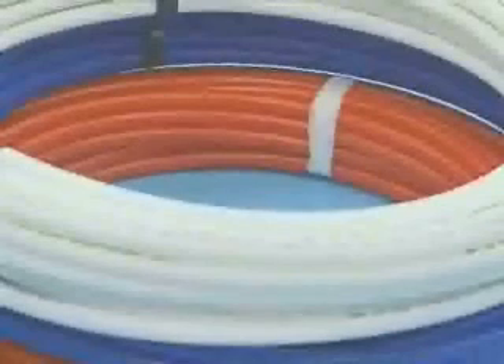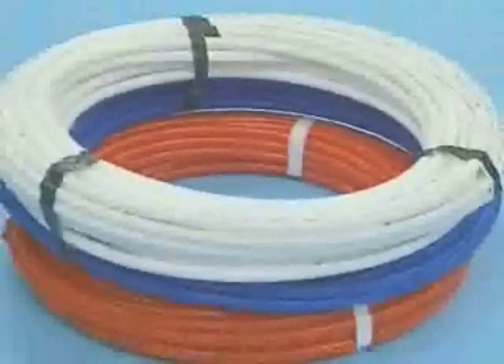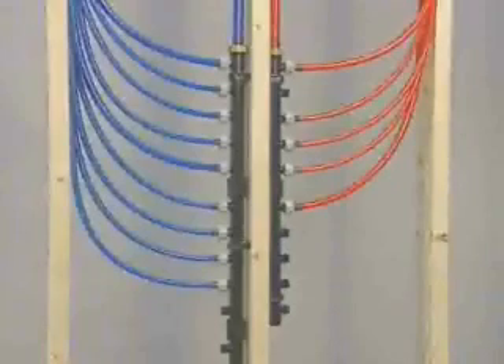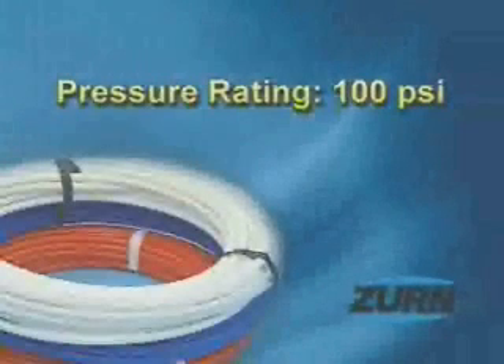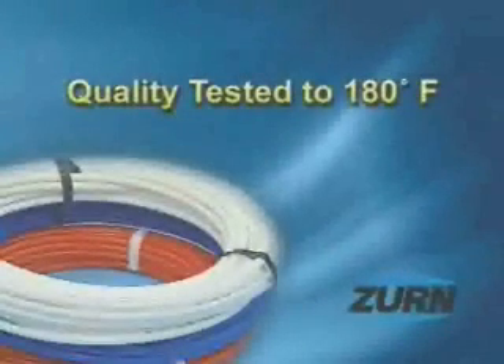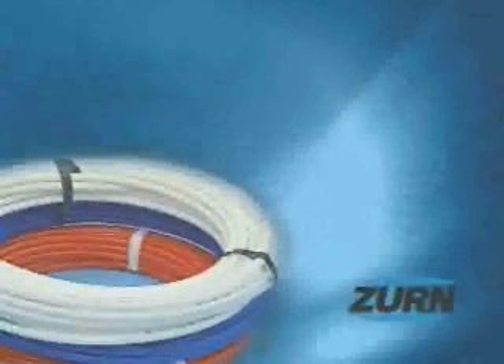Zurn PEX tubing is available in white, red, and blue. These color options make color coding of hot and cold water lines easy if desired by the plumber. The pressure rating for Zurn PEX tubing is 100 PSI, more than enough for residential plumbing applications. It is also safe because it is quality tested at temperatures up to 180 degrees Fahrenheit — 40 degrees higher than most residential plumbing systems require.